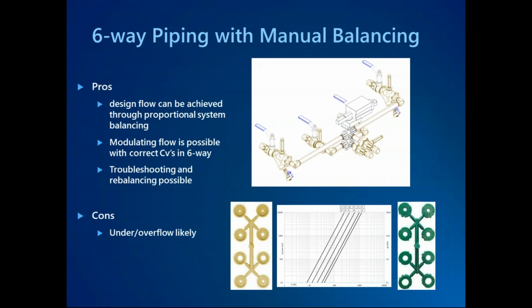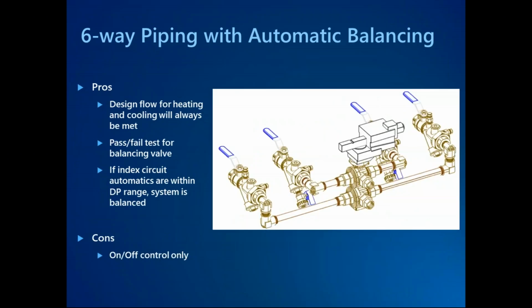So there again, there are applications out there for this, but I think for the most part, especially out west here, we're seeing the next solution becoming the most common, most prevalent design out there. And that is incorporating automatic balancing valves with the six-way control valve. Pros are we're going to provide the GPM that the engineer specified up front, and the automatic balancing valves are going to compensate for any pressure fluctuations of other things in the system opening and closing to maintain the constant GPM that you need. From a commissioning standpoint, all you need to do is identify the index circuit for both the heating and cooling run. Most likely it's going to be the same six-way for both heating and cooling.